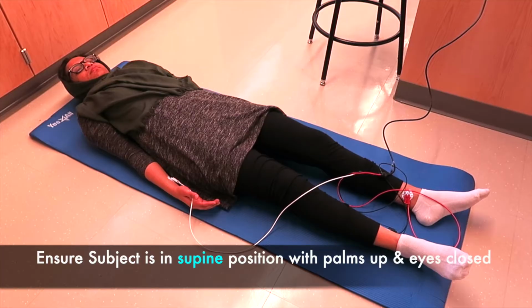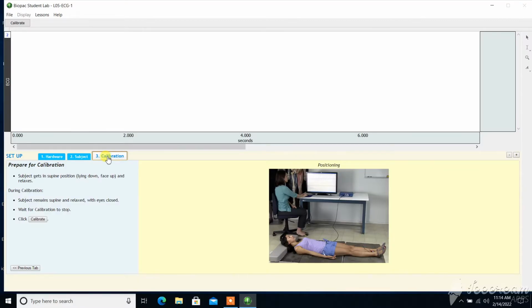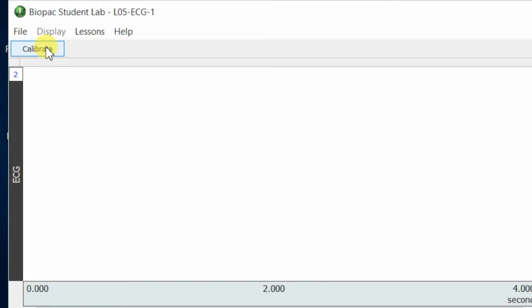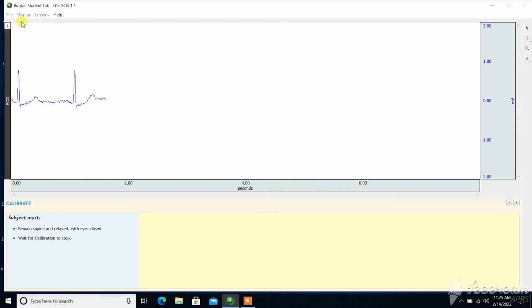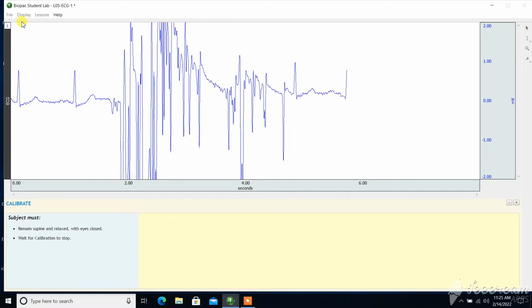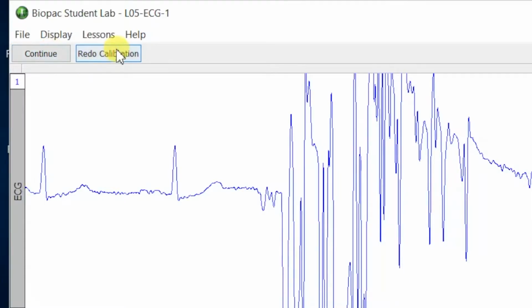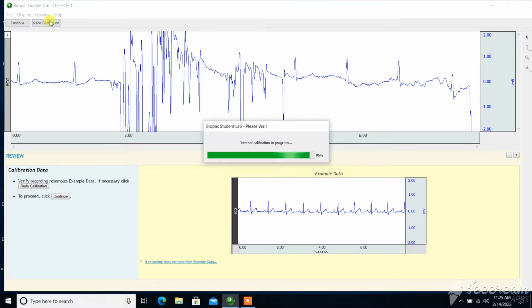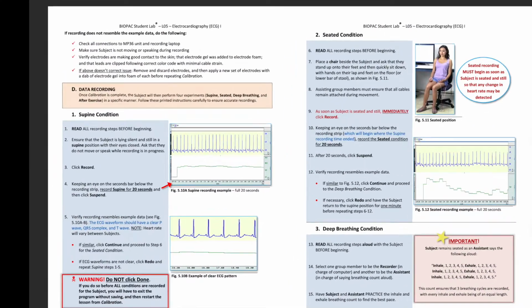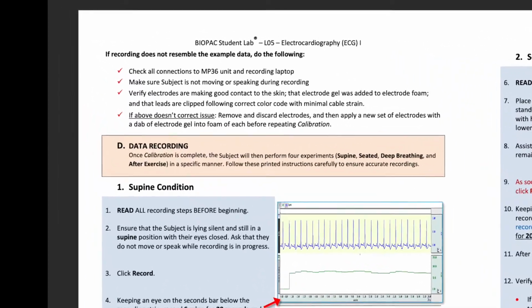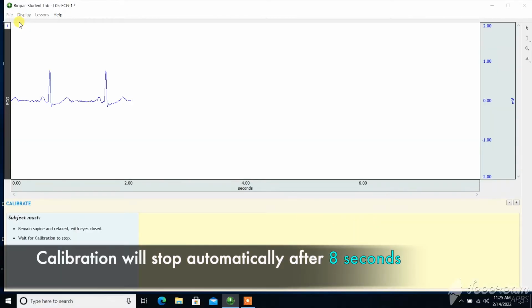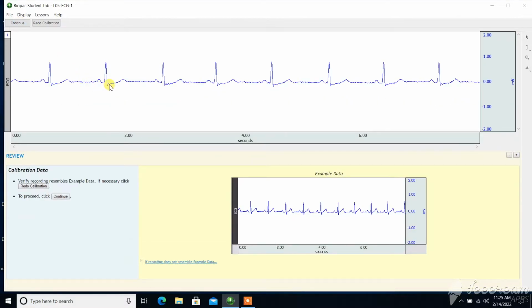Ask that the subject remain relaxed with their eyes closed and that they do not speak or move while calibration is in progress. Click Calibrate at the top of the screen and wait for it to stop automatically after 8 seconds. You should see a clear ECG pattern repeat on the screen during this time. If the ECG pattern is unclear, click Redo Calibration and review the troubleshooting checklist in the lab instructions before repeating steps 1 through 5 and redoing calibration. If the ECG pattern is clear, however, and you can make out the P waves, QRS complexes, and T waves, click Continue.